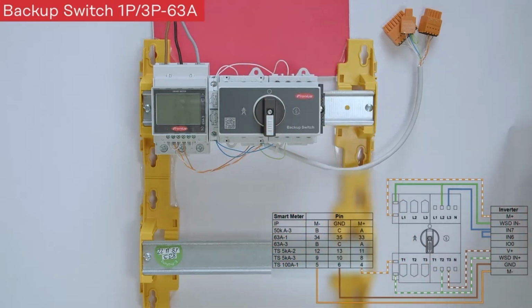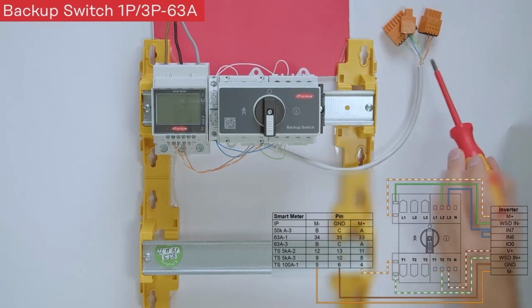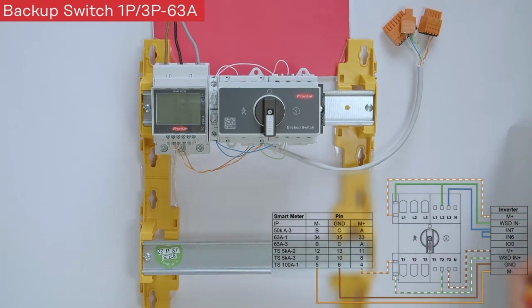Please note that whenever you have already installed, for example, a Cat6 cable between Fronius inverter and smart meter, most of the times you can use the open pins that are still left here, the open lines, to make sure that you can install the WSD contact as well as I6 and I7. So this has the advantage that you don't need an extra cable coming from the backup switch to the inverter, but you can most of the times use the existing line to install the backup switch.